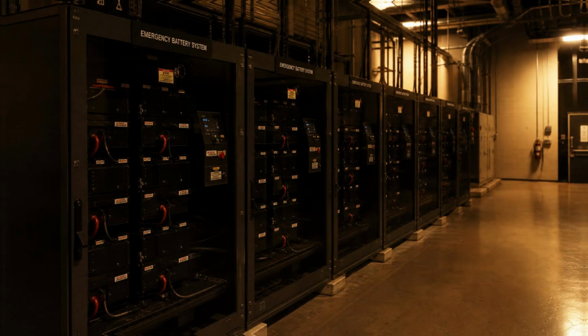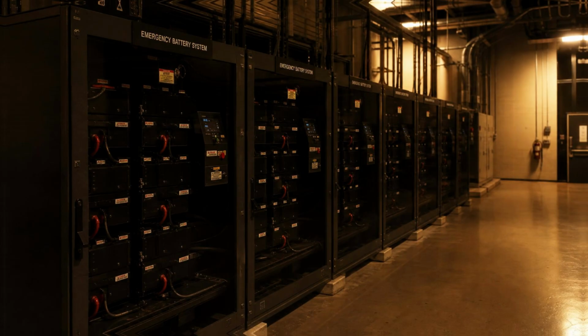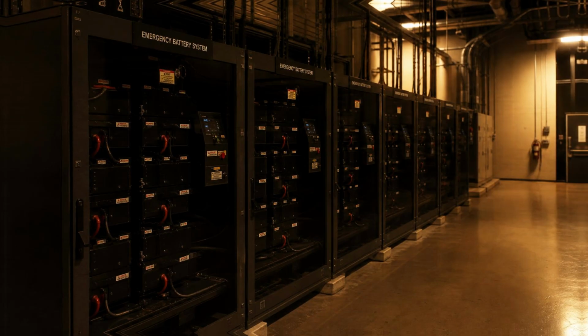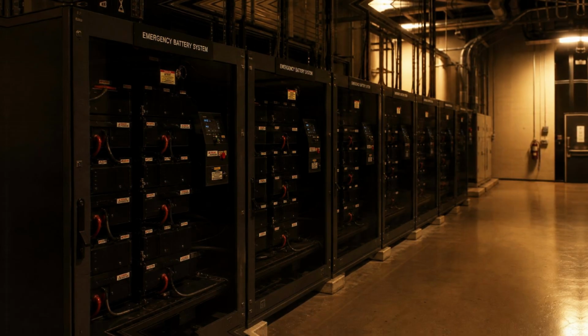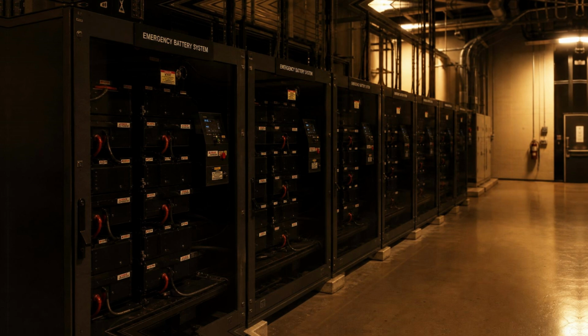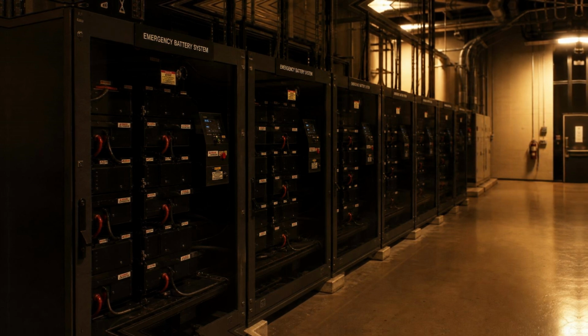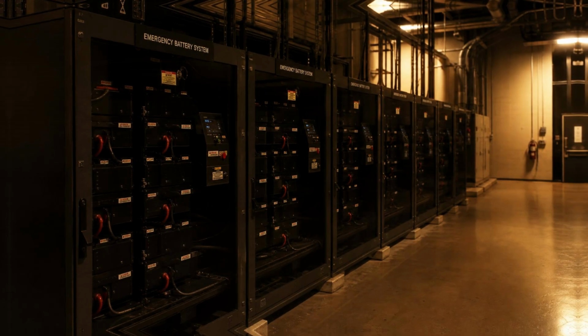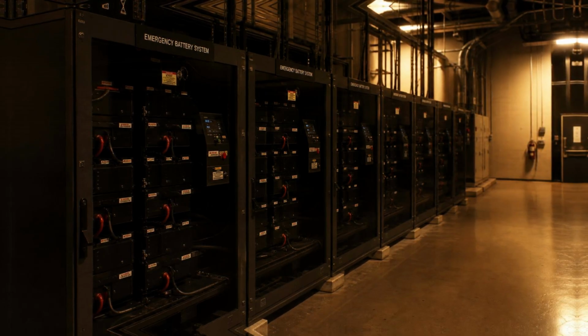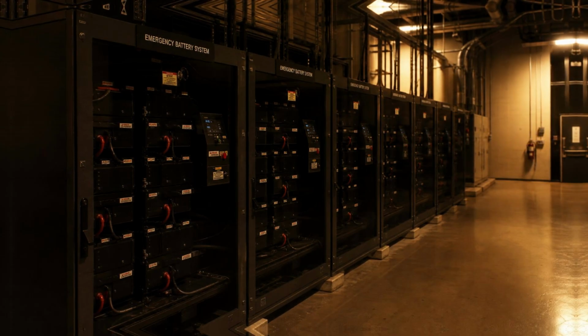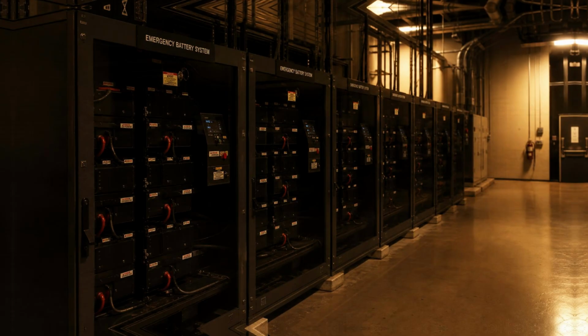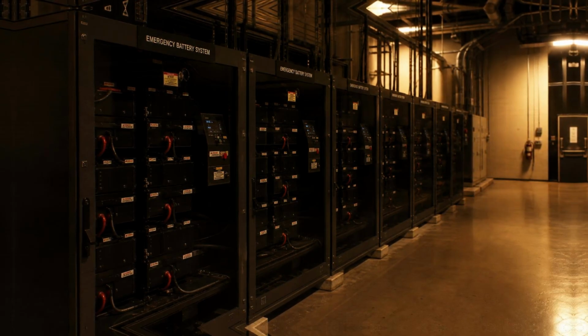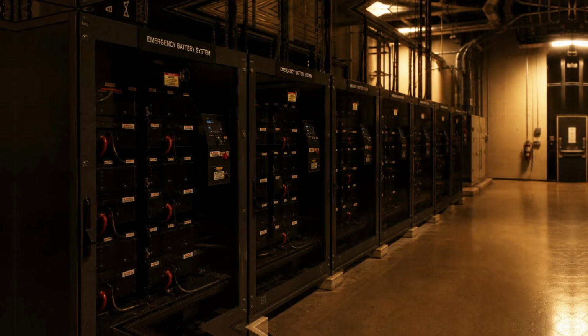This battery, like all the batteries in the system, is kept on a continuous trickle charge during the long periods of standby. A small charger connected to utility power delivers a gentle and steady current that keeps the battery at full capacity without overcharging it. The charger works so quietly and draws so little attention that it is easy to forget it is there. But it is there. Every hour of every day, during all the standby time between exercises and between actual emergencies, the charger is doing its work, keeping the battery ready, ensuring that when the start signal finally arrives, the energy to respond to it is fully present.